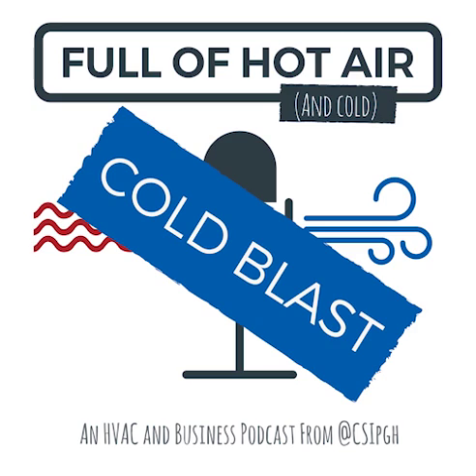One rule of thumb when you're looking around a house: most basements in our area have an exposed duct system. If you have a 3-ton unit, you want to see at least twelve 6-inch runs off of that, because the formula we all learned in school was 400 CFM per ton. Now, with efficiency and dehumidification being a big thing, the other number you could work off is 350 CFM per ton. But traditionally, for every ton of air conditioning, you need 400 CFM.